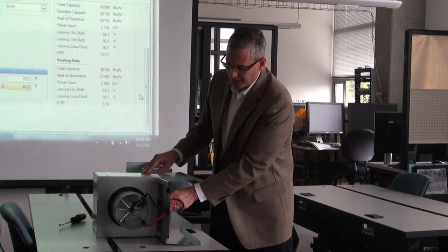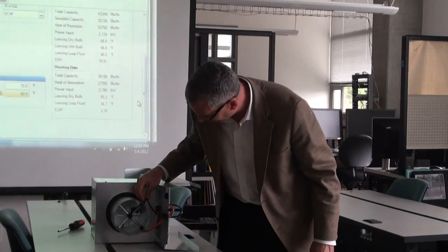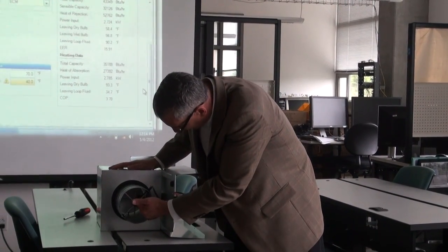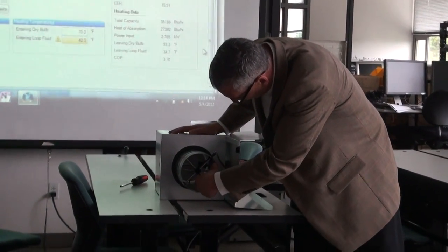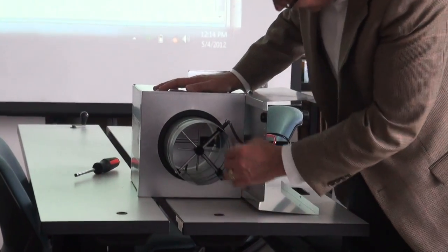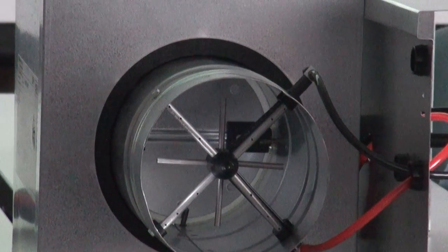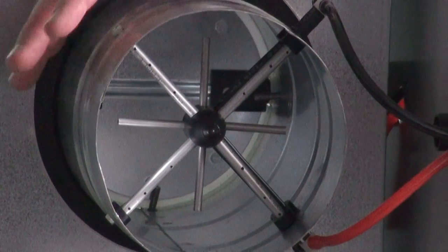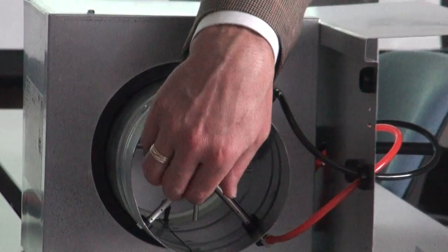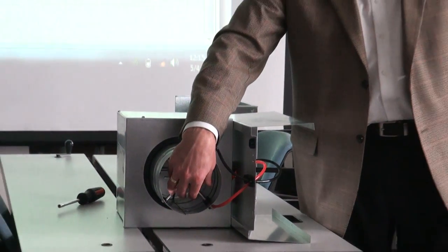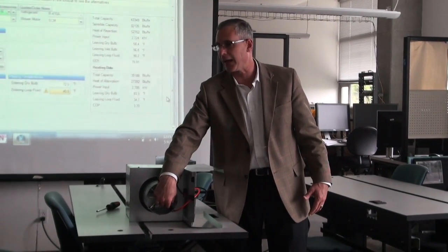And these are pressure independent boxes. In the past, they didn't have that, and that became a big problem. And so they devised sensors that pick up velocity pressure in the front and on the sides, static pressure. And these holes are placed in such a way that it can average very precisely the associated pressure readings, the difference readings, and through a formula figure out what that volume of air would be at any given time.